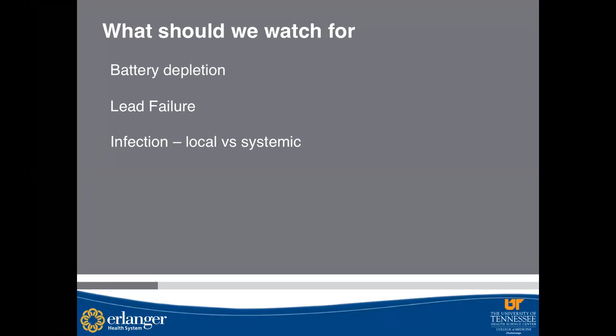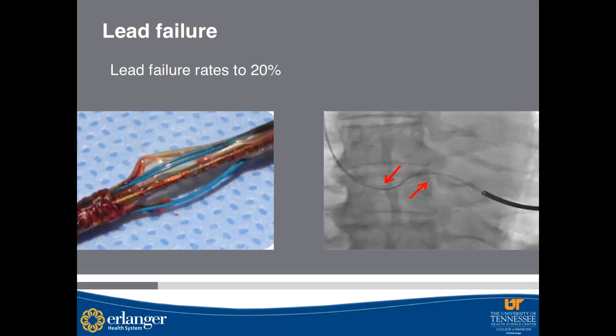When we watch for lead failure, some of the things that we can see is that the insulation, as you see in this picture, the actual outer coating of the insulation can go bad, and we get these wires that are actually supposed to stay inside actually come out of the lead itself and be exposed and not function appropriately. And you can see this here under X-ray where the wire is kind of coming outside of the insulation or outside the encasing of the lead itself. And this can happen actually up to 20% of the time over the course of a patient's life. And so that's pretty high. And so there's a good reason for us to continuously monitor these devices as time goes on.